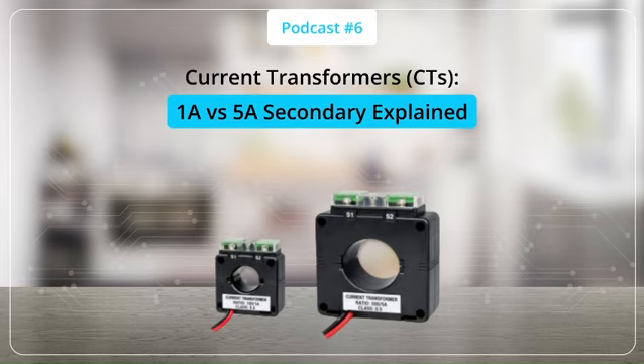The secondary current also affects accuracy. In systems with long cable runs, higher current like 5A leads to greater losses, which can reduce accuracy. In such cases, 1A CTs provide more reliable performance, especially in remote installations like substations.